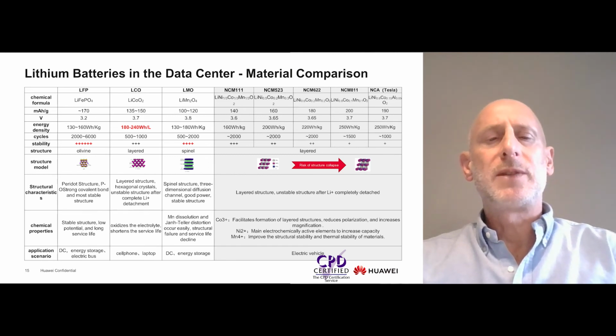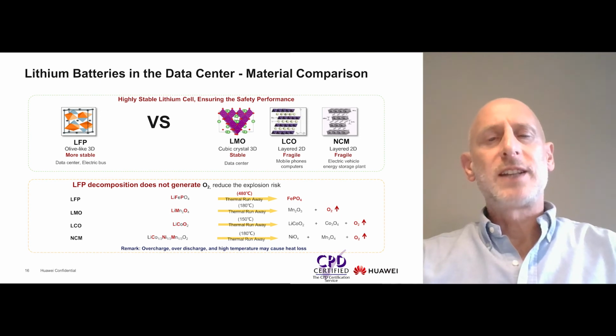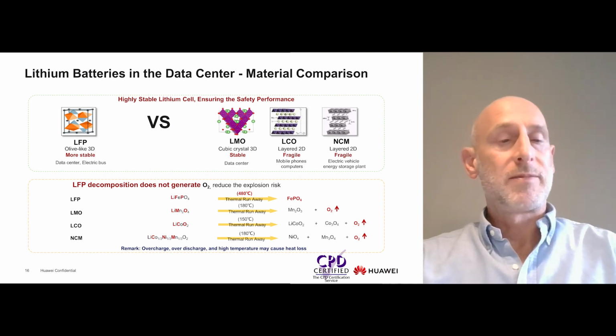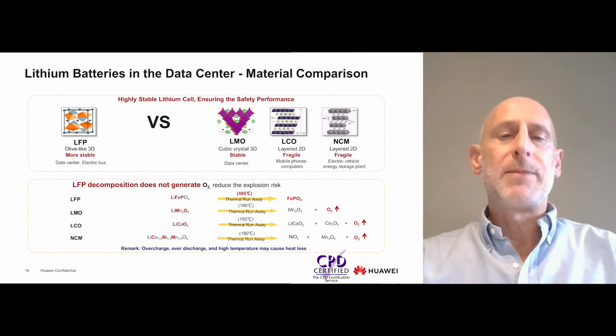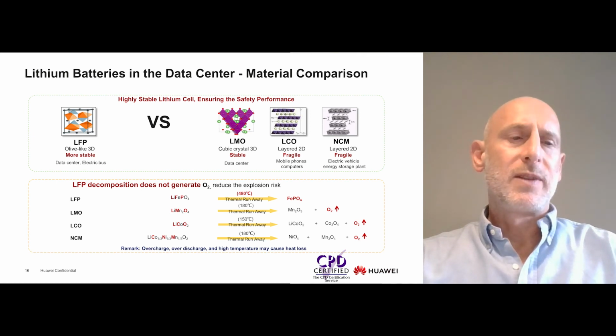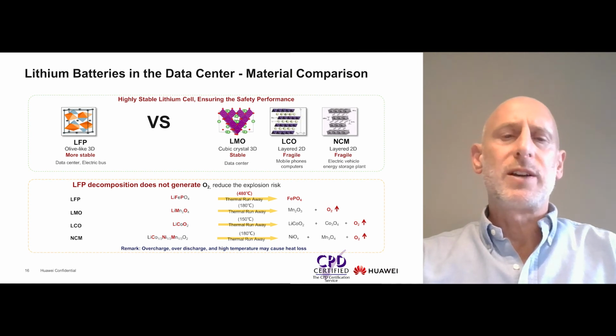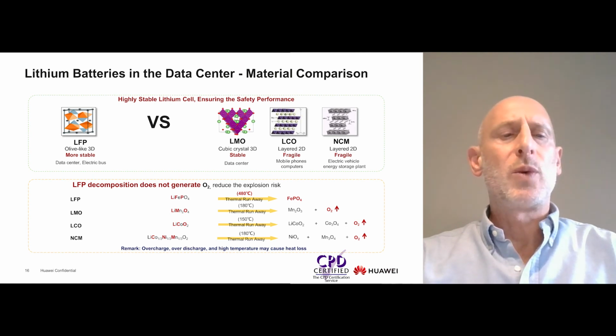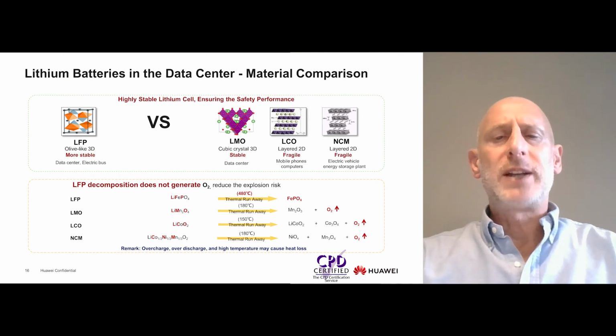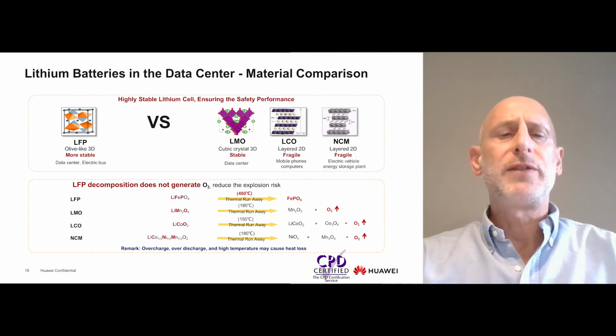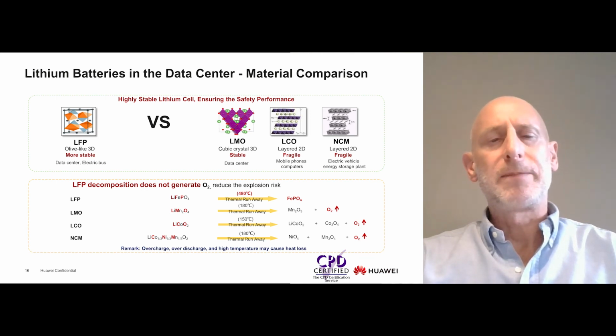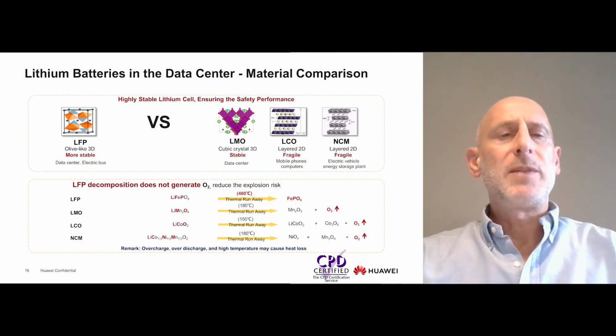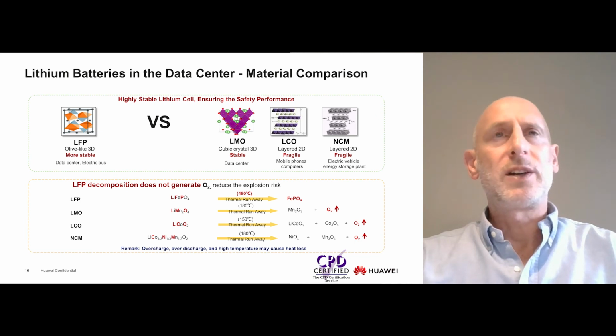The important takeaway here is that different types of lithium-ion have different characteristics and are applied to different applications. As discussed, chemistry, performance, cost, and safety characteristics vary across types of lithium-ion batteries. In terms of molecular structure, both LCO and NCM are layered 2D structures, which are relatively unstable. Although LMO is in a cubic crystal 3D structure, it is relatively dangerous to use because it is prone to thermal runaway in high temperature environments, and oxygen is generated when thermal runaway occurs. The data shows that the thermal runaway temperatures of LMO, LCO, and NCM are between 150 and 180 degrees centigrade respectively, and all of them generate oxygen. Lithium iron phosphate (LFP), on the other hand, is more temperature resistant and does not produce oxygen when thermal runaway occurs.